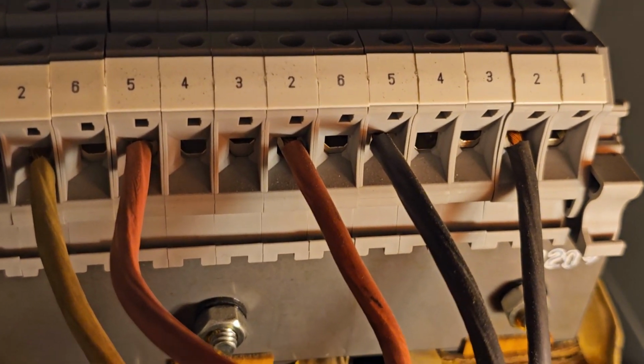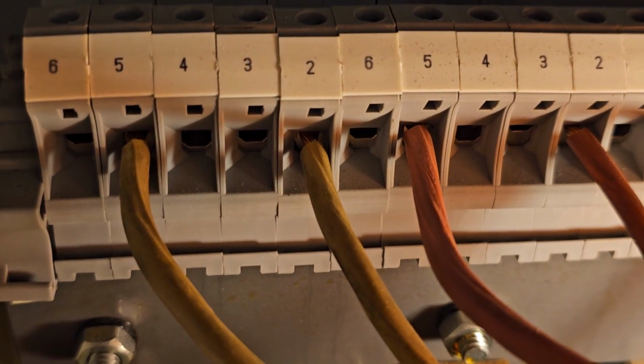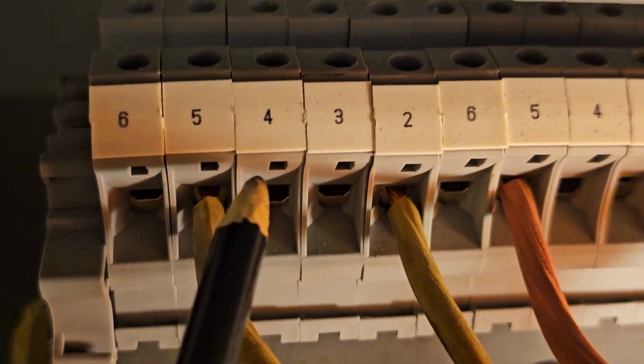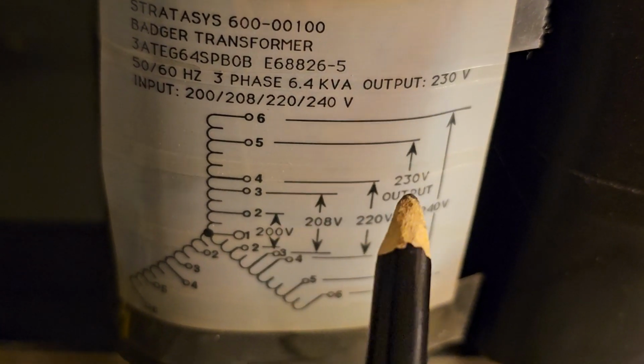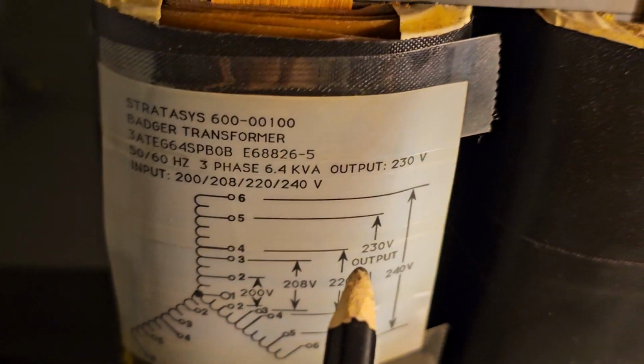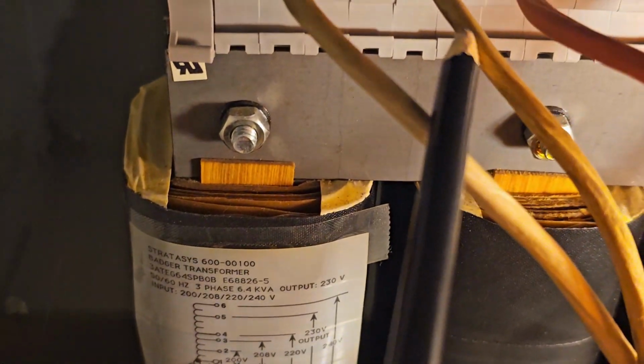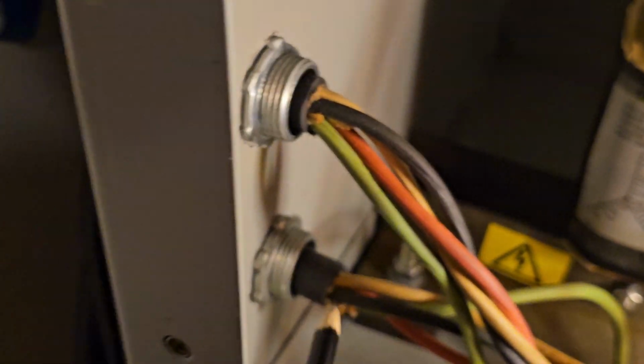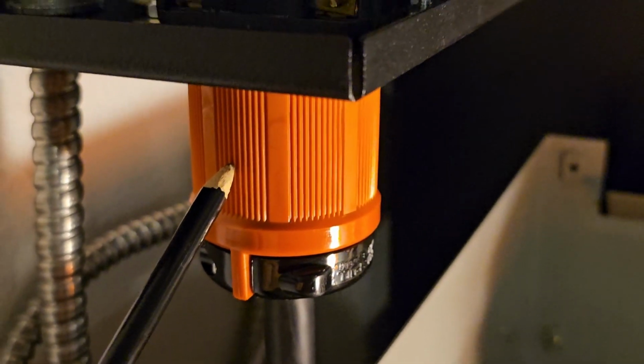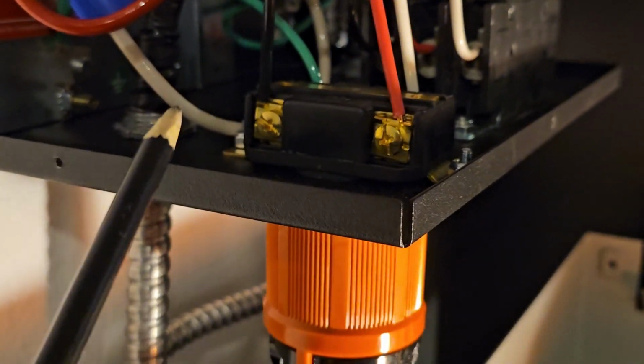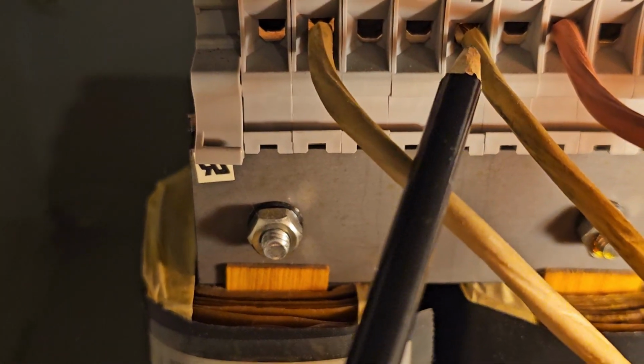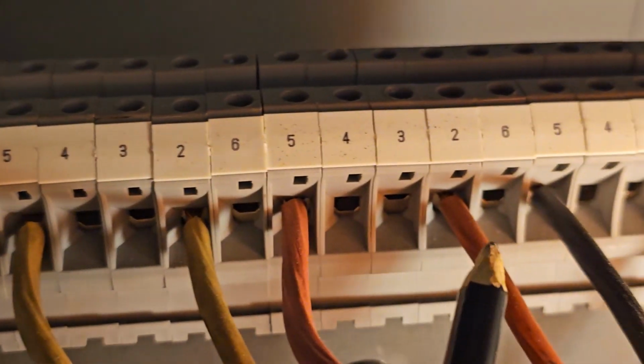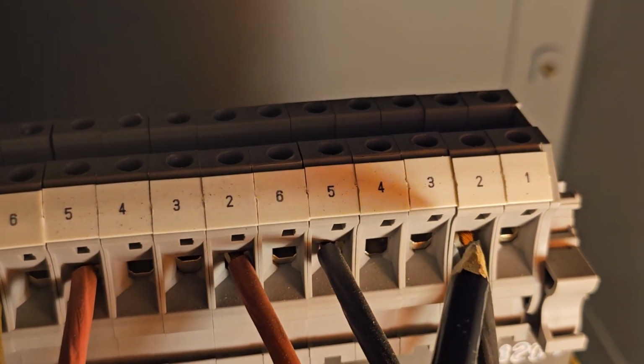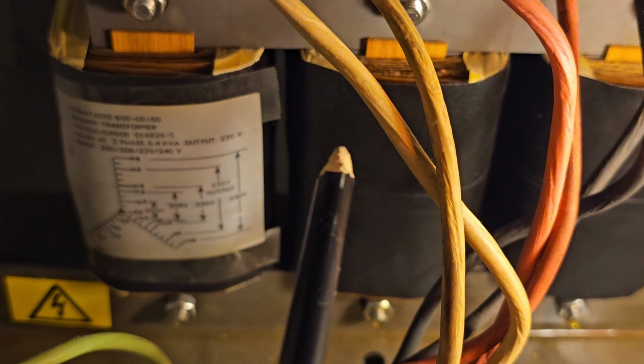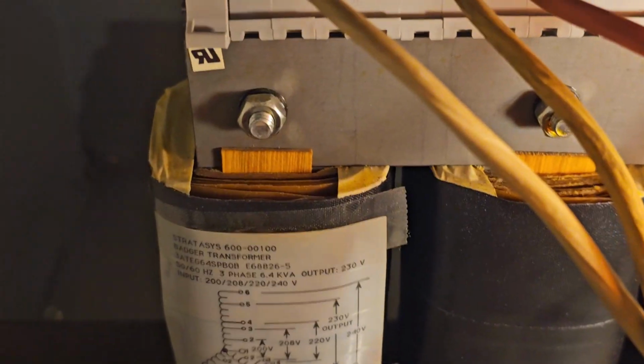Now, I look at how this is wired, and I see the white wire on number 5. Number 5 is good, that's the output for 230 volts. So where's the other white wire? Because one is coming into the transformer, and one is coming from this group of wires here that attach to this plug in the phase converter panel. So I look and I see it's connected to number 2. The red is connected to number 2, and the black is also connected to number 2. There are 3 transformers in here, one for each of the 3 lines.